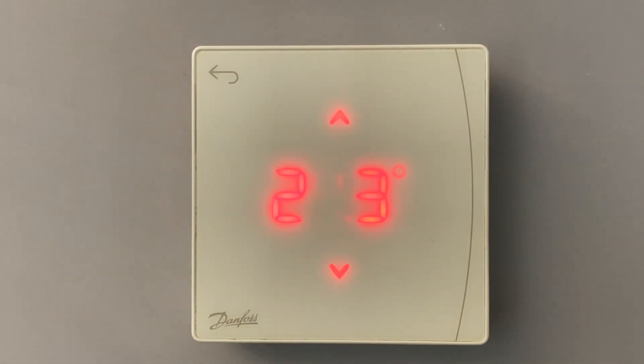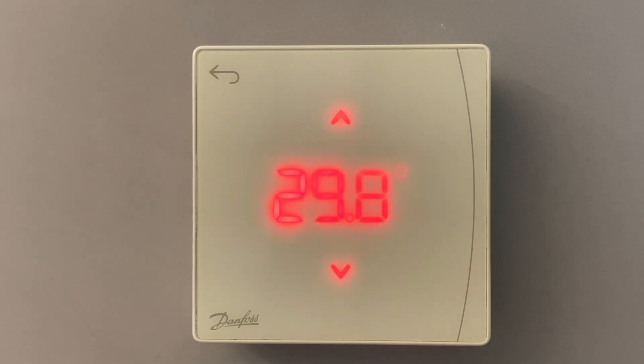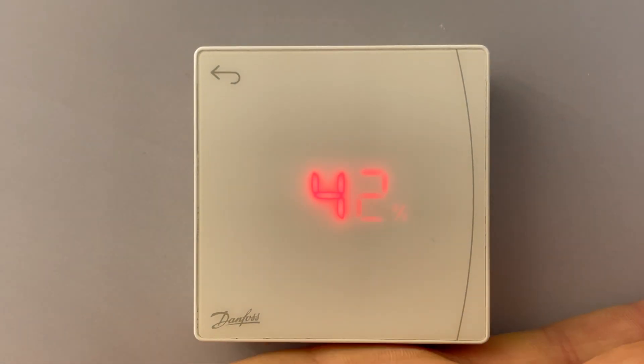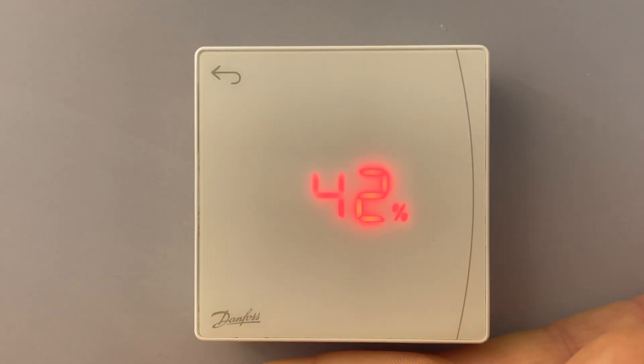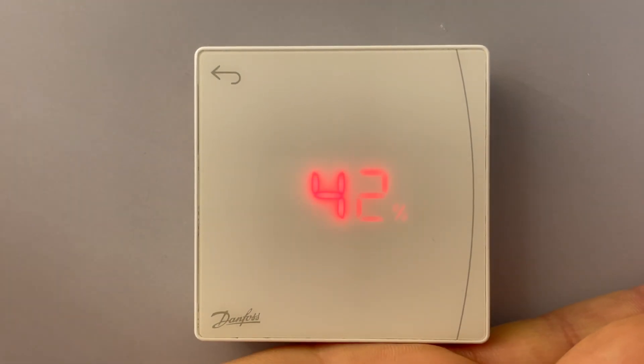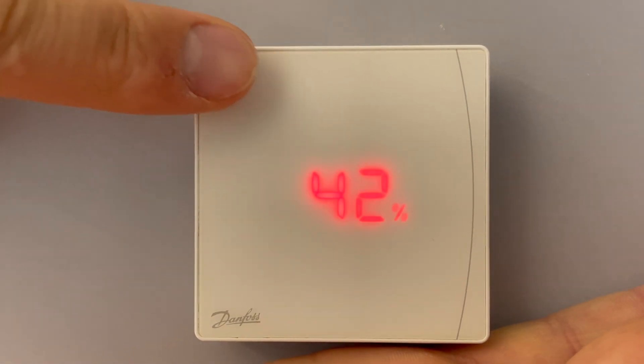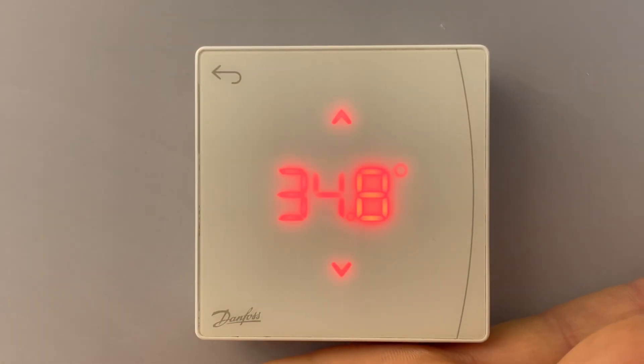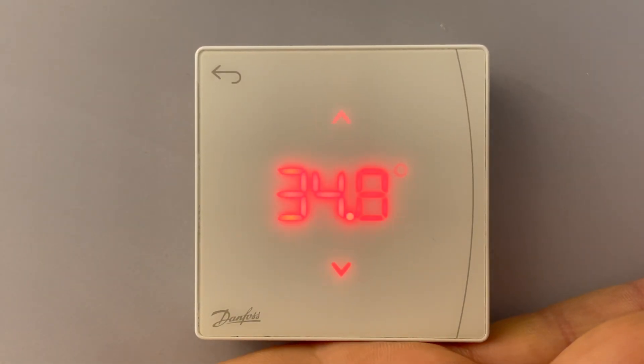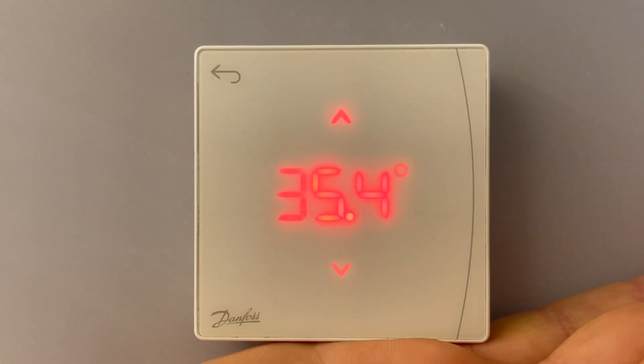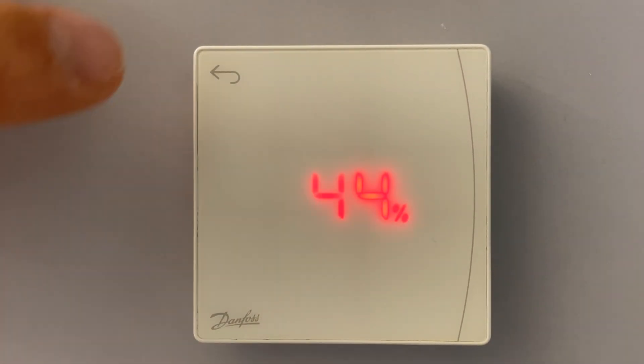It's very easy to check if it is measuring floor. If I put my hand right there and push the thermostat, it will measure my hand temperature. If I take my hand out, it will measure floor.